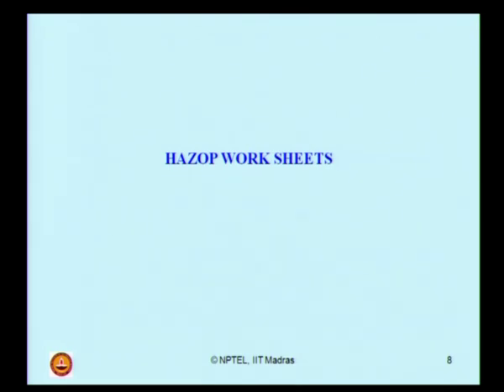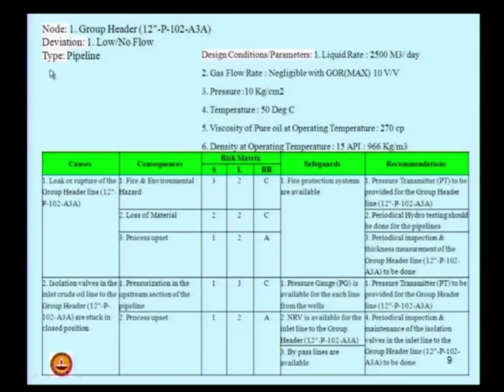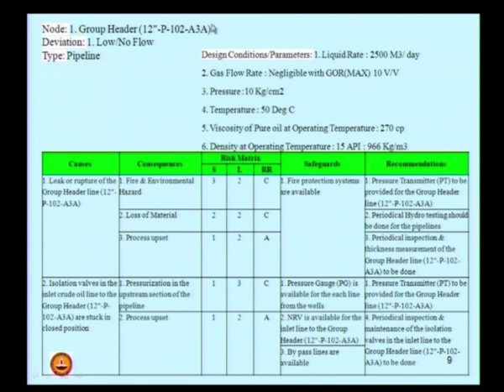Presuming you have understood the functioning of a group gathering station and the importance of the selected nodes, let us now take forward the HAZOP worksheets prepared using PHA Pro software. The first node is identified and named node 1. The software output says node 1 is the group header, which is a 12-inch pipe designated 102A3A class. The deviation from the design intent is low or no flow, and the type is a pipeline. The design conditions are: liquid rate 2500 cubic meters per day, gas flow negligible, operating temperature 50°C, pressure 10 kg/cm², viscosity 270 cP, and density 966 kg/m³.